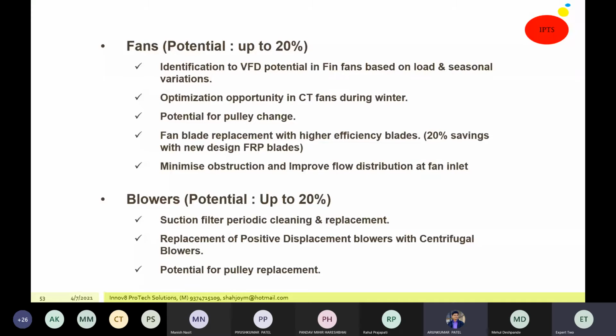So for the fans, you have a lot of options, and I observe about 20% saving can be possible if you optimize your fan by reducing the obstruction, improving the flow distribution, then replacement of the blade with a high efficiency blade. So these are the various options available for the engineer at the time of design as well as at the time of normal operation to improve the efficiency of the fan. Blowers are almost a similar thing. You have to clean the suction filter, which offers a lot of pressure drop.